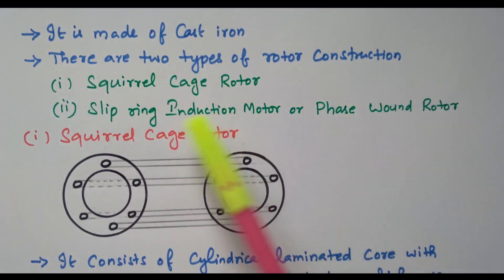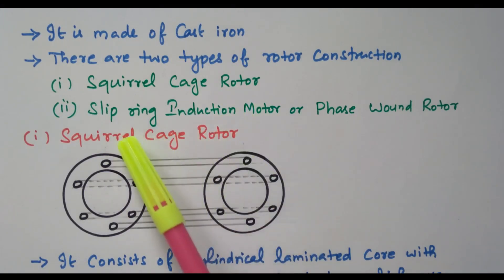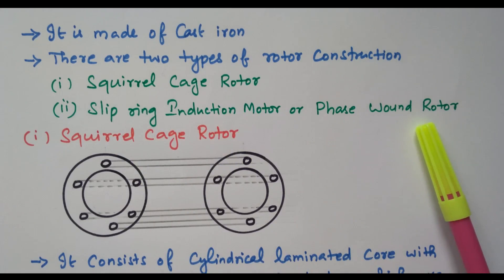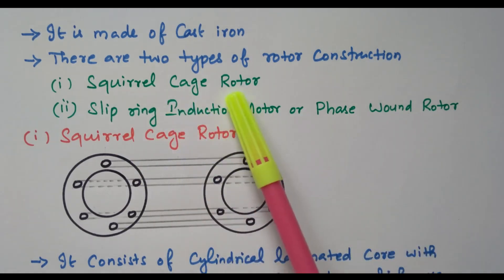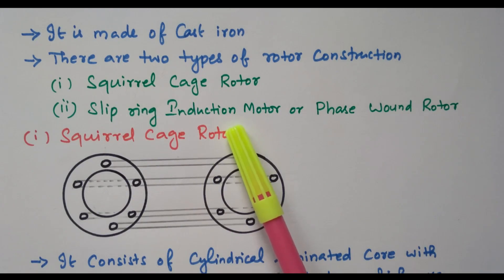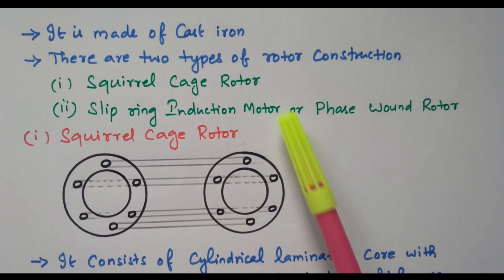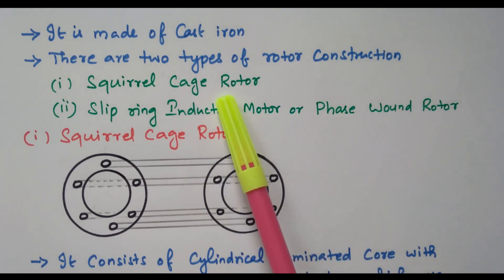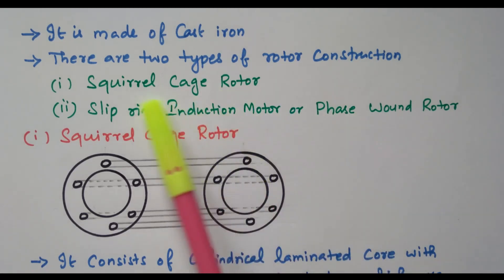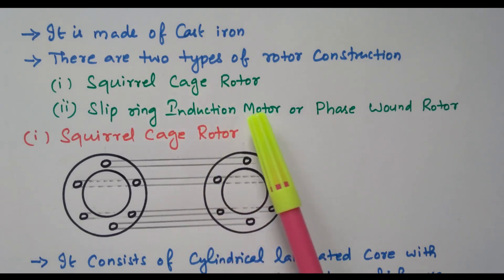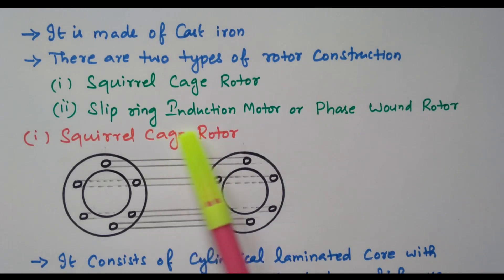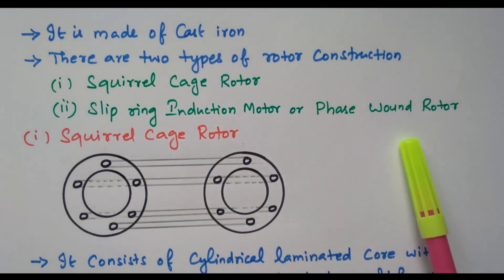There are two types of rotor construction available. One is the squirrel cage rotor, and the other is the slip ring induction motor, also called the phase wound rotor. In the squirrel cage rotor, copper bars are available. In the slip ring type, a separate winding is available — that is the major difference. The copper bars in the squirrel cage rotor are permanently placed and cannot be modified, whereas the slip ring winding can be altered.